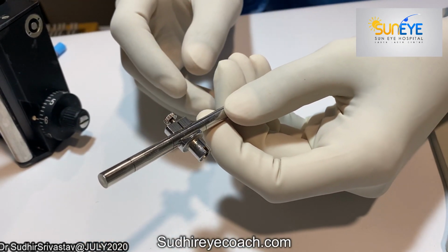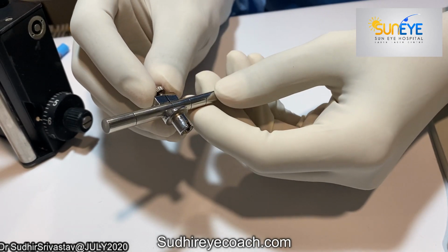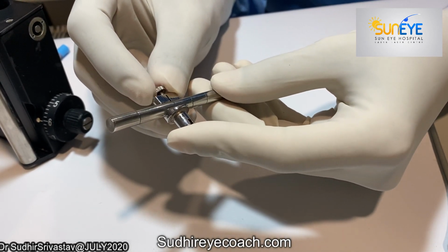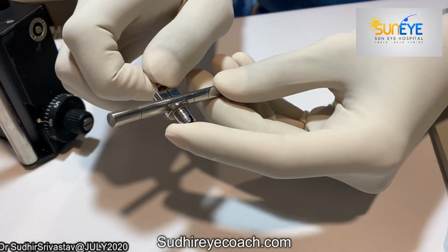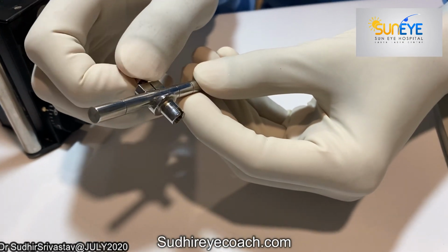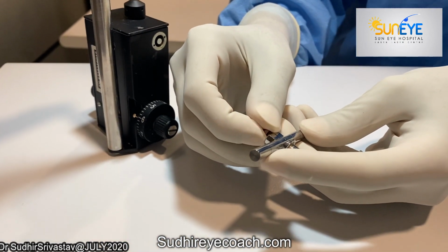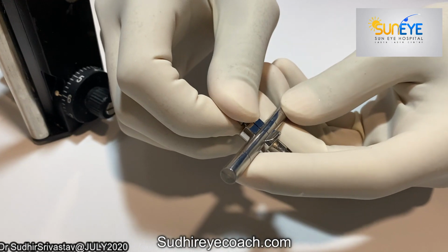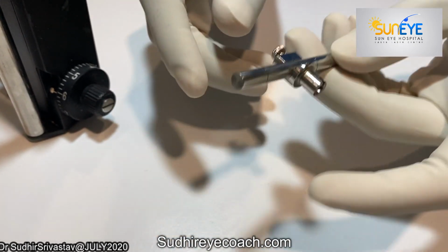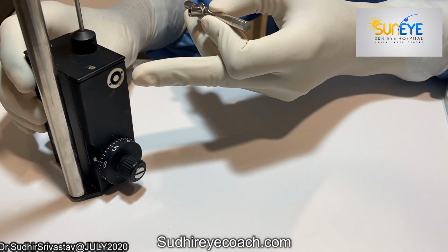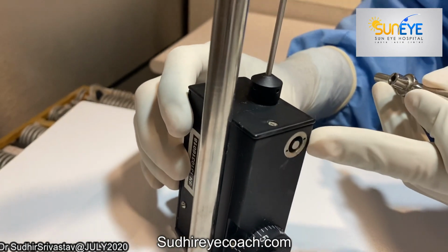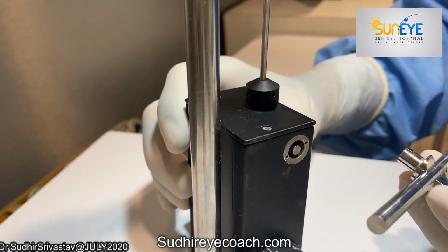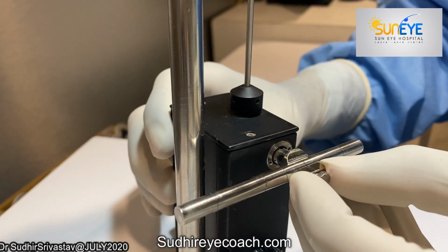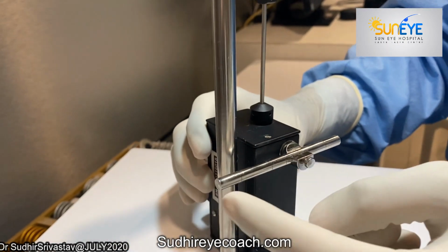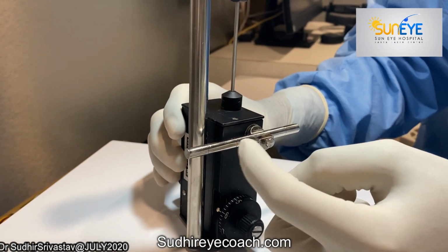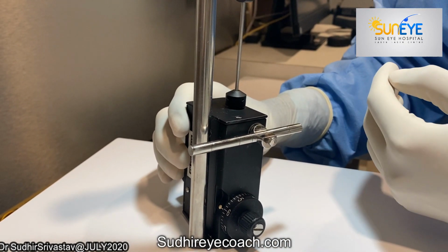Now to start the calibration, it has to be tightened at the 20 millimeters of mercury marking, like this. After tightening it at the 20 millimeter marking, we have to apply it on the groove which is present on the upper side of the applanation tonometer. This is the groove, and we have to apply it like this. Now the longer arm has to face towards the examiner. As you can see, this is the orientation while doing applanation tonometry.